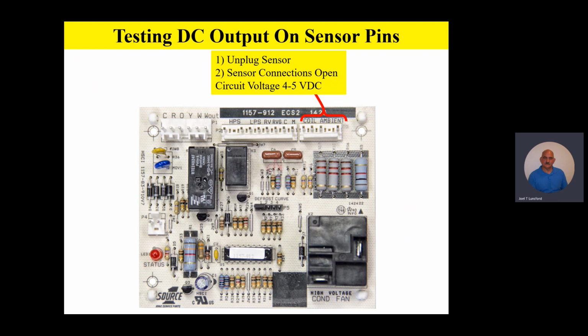And if you're having issues with the defrost control and you think it might be a sensor, it's probably going to be a sensor, because chances are that the sensor has gone bad and it's not the control board. I know a lot of times a contractor has the attitude, well, if I replace the sensors, I might as well replace the board, or if I replace the board, I might as well replace the sensors. But a lot of times we find out that there's nothing wrong with the boards on ones that have been returned for warranty. So we're always going to suspect the sensors before we suspect the board. So one more time, if we've got 24 volts on the board and we have 4 to 5 volt DC on our sensor pins without the sensors plugged on, chances are it's not the board.